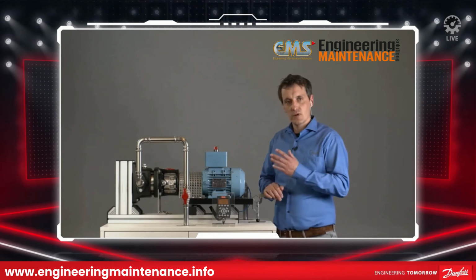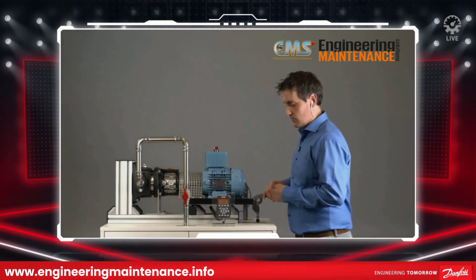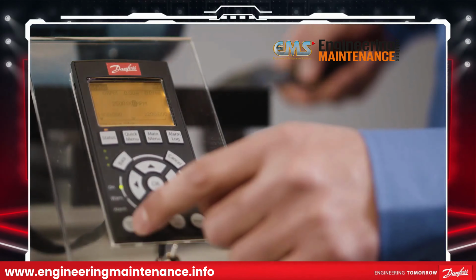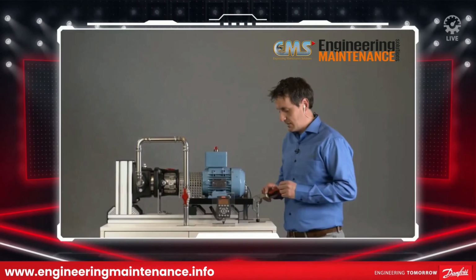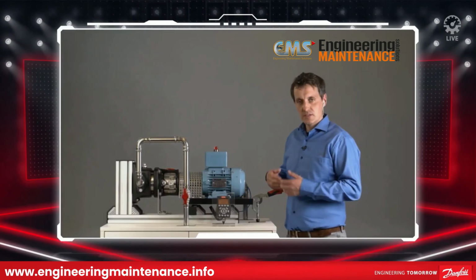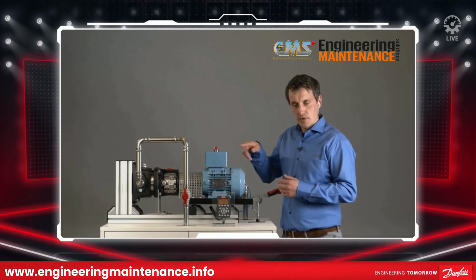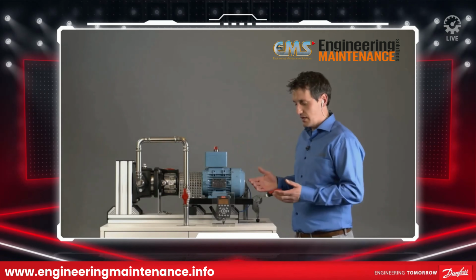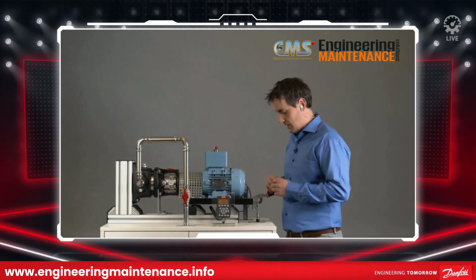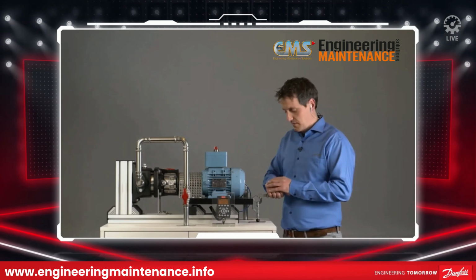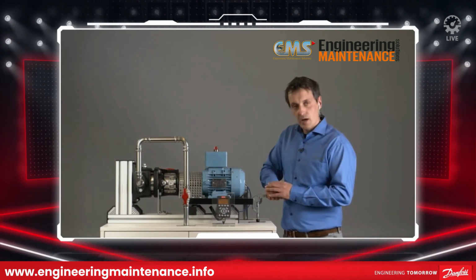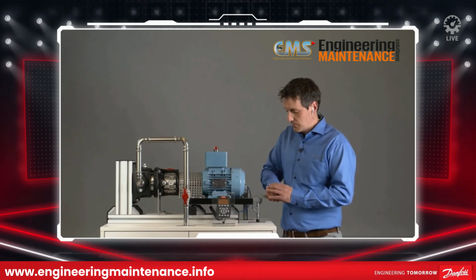So let's look at what the drive is doing in this case. For this, I will start the drive. So now the system is running its application. It's pumping the water through the pipes. Everything is okay. The drive is happy. But now let's simulate the failure. So I'm creating this misalignment now.